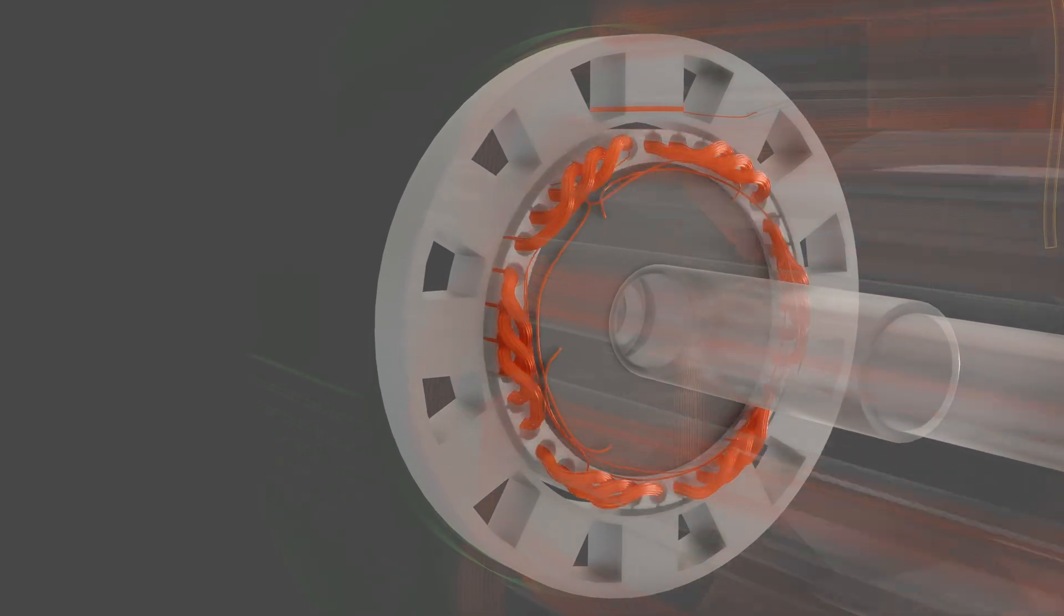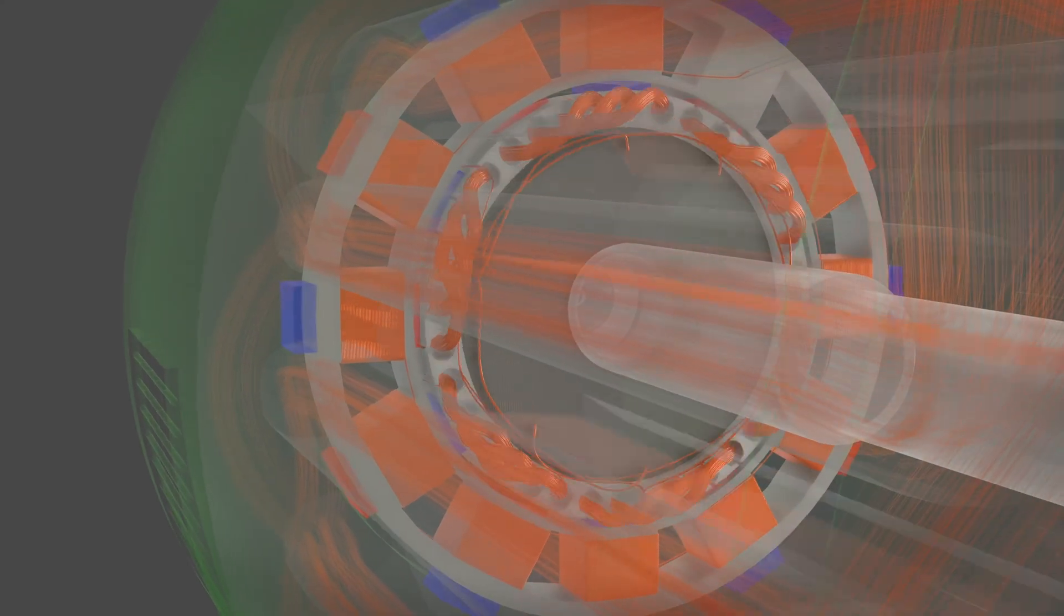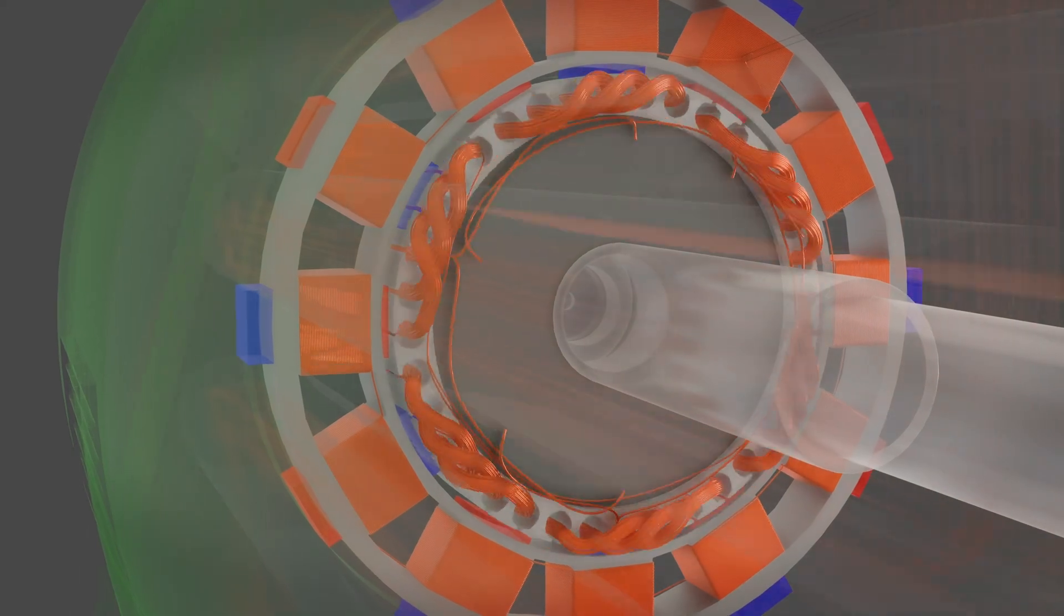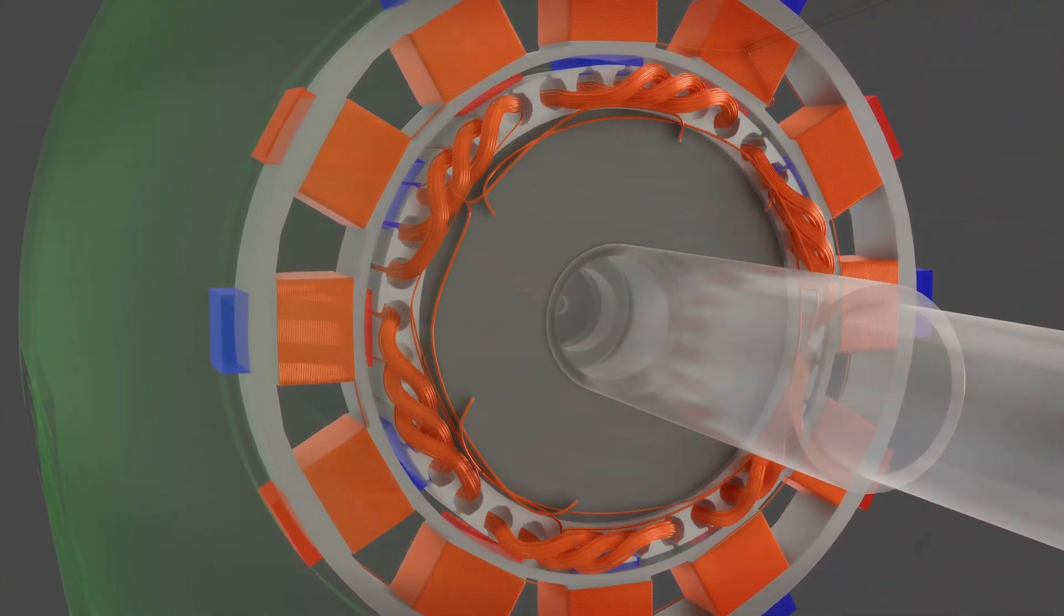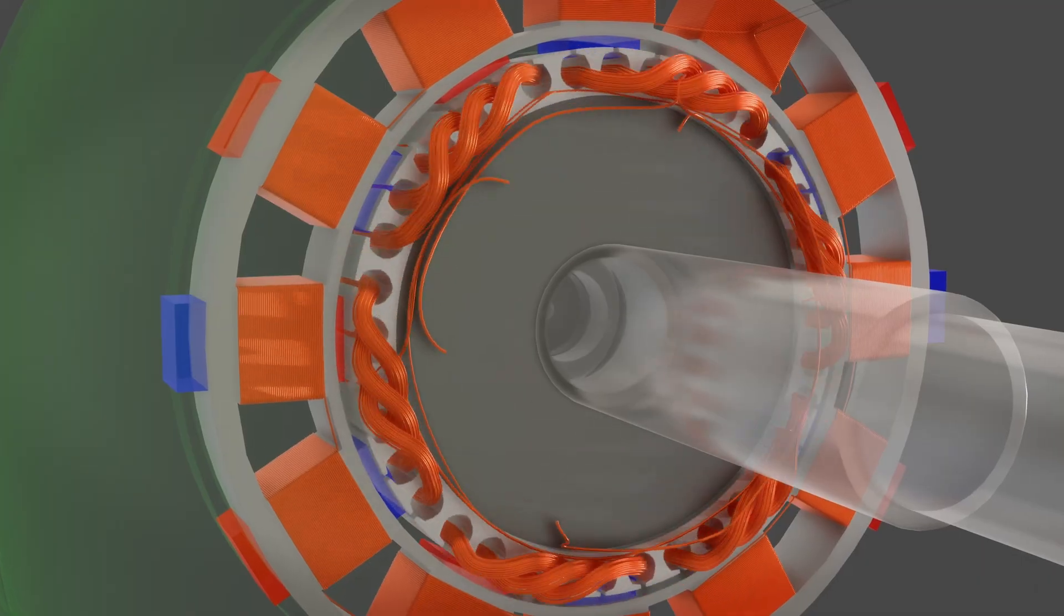The exciter stator winding is done similar to the main alternator rotor, where coils are wound in alternating clockwise and counterclockwise directions to create alternating magnetic poles. The exciter rotor coil winding is done similar to the main alternator stator, where three coils are positioned 120 degrees apart.